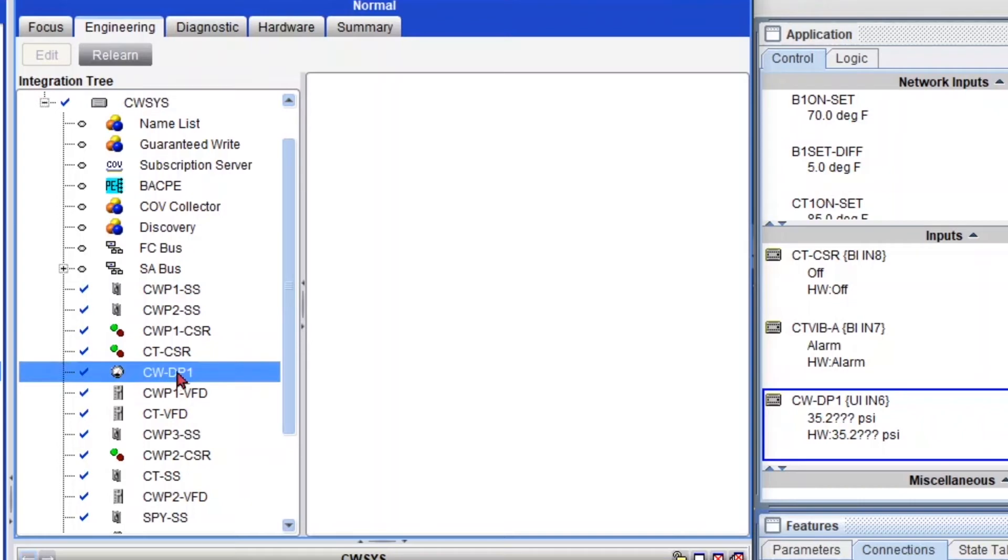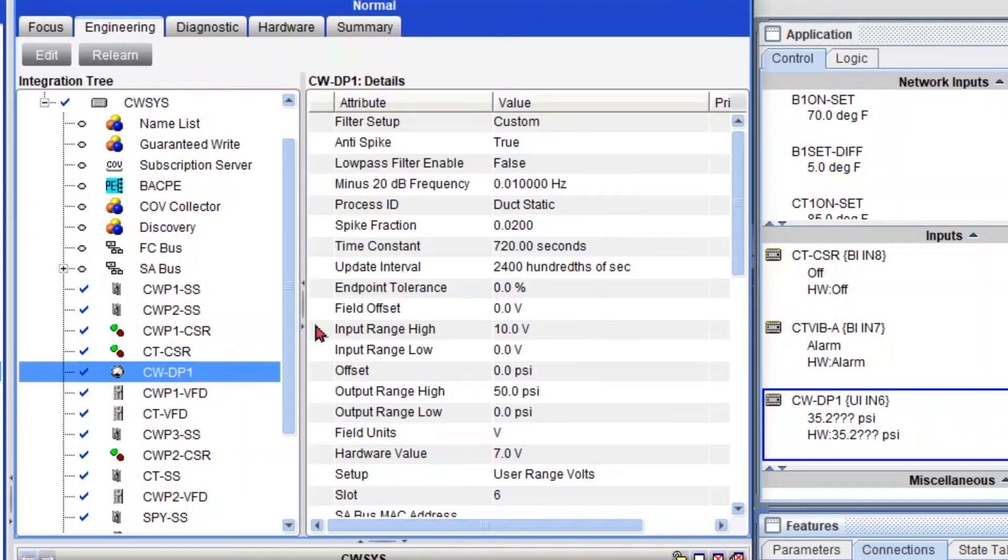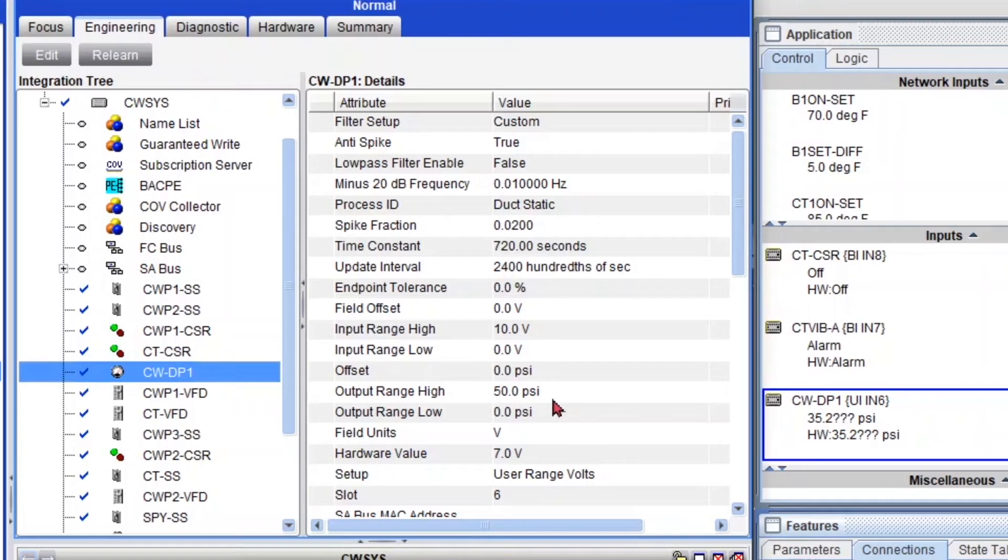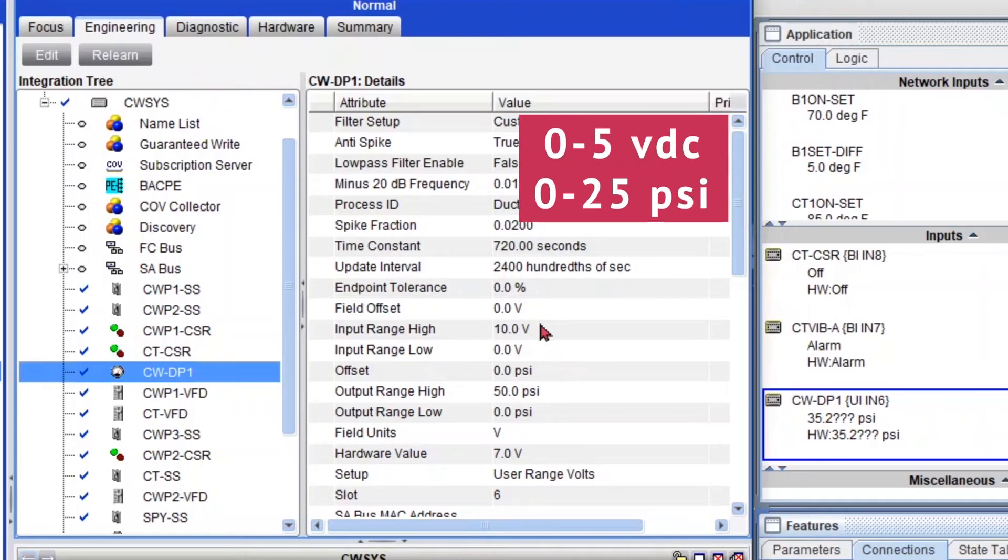Double click on it. And we can see that it was configured as a 0 to 10 volt sensor and a 0 to 50 PSI range. And let's say that the actual sensor that was installed, it's a 0 to 5 volts and a 0 to 25 PSI.